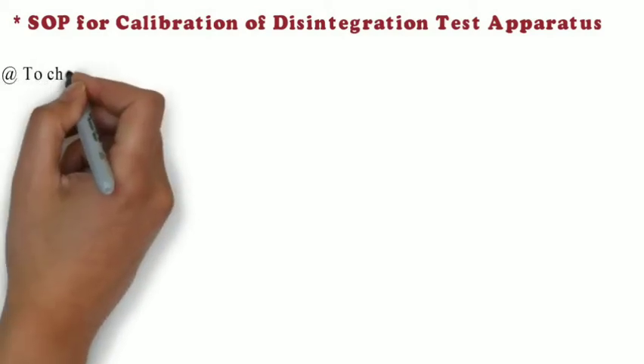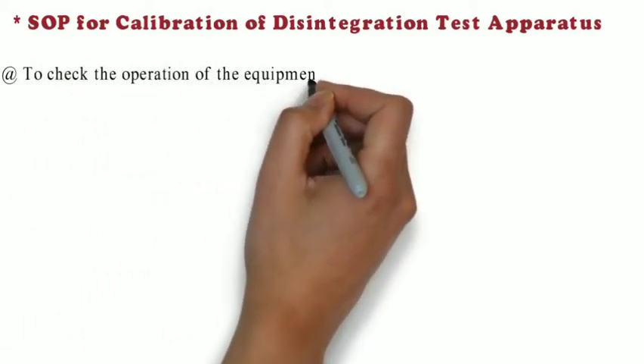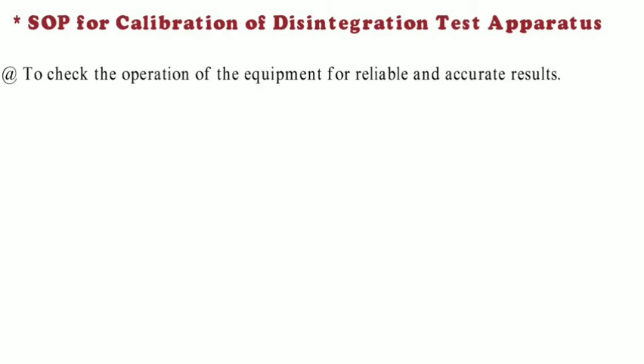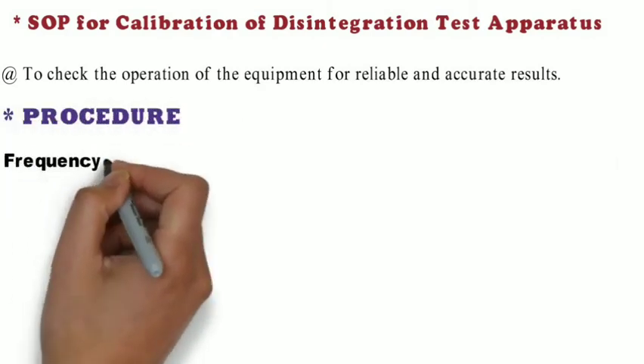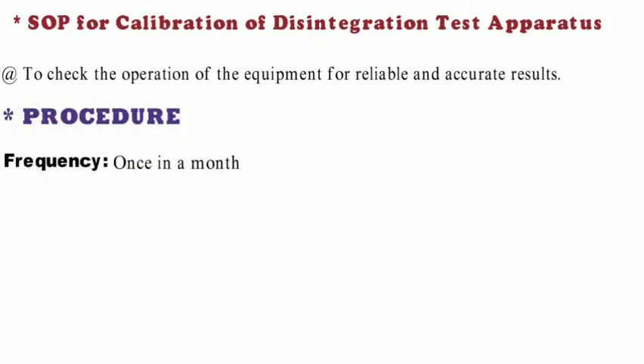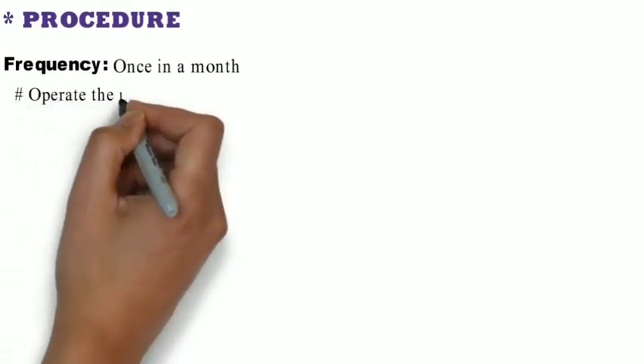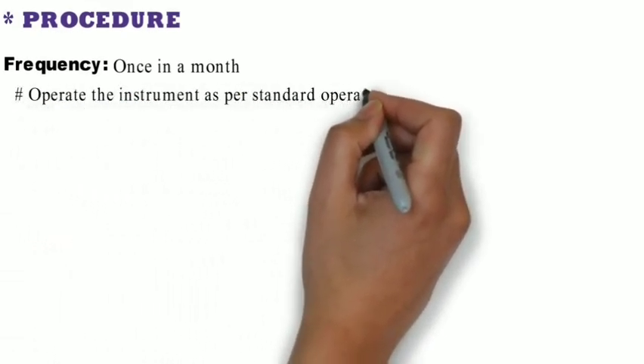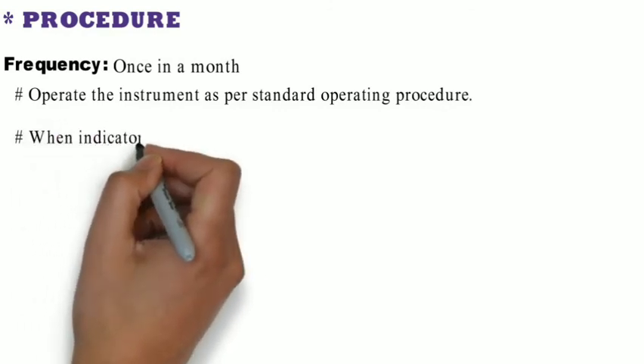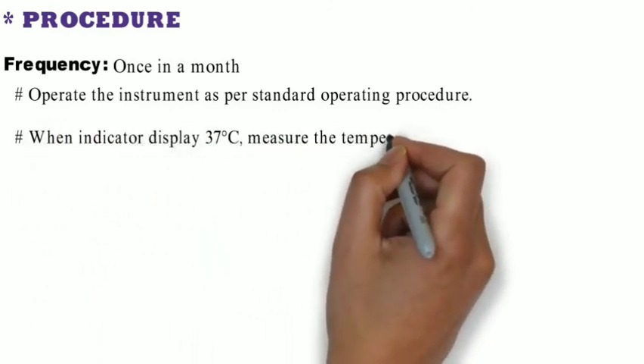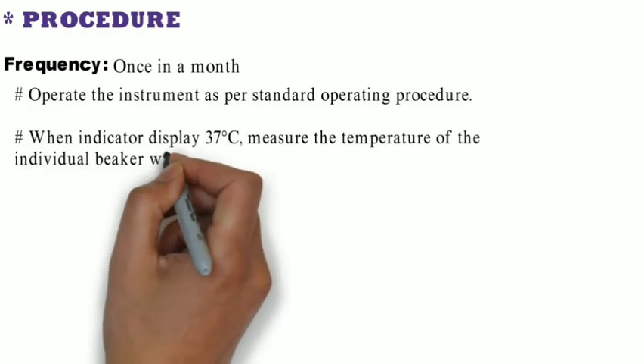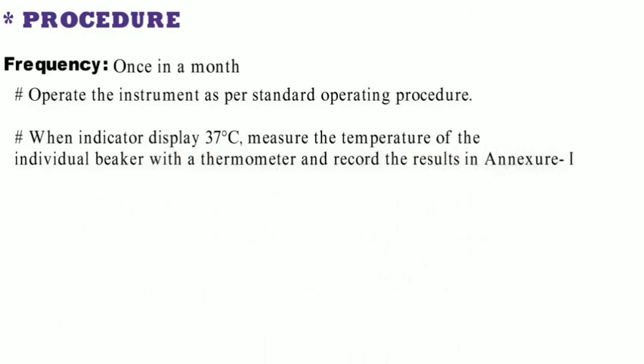This is the important portion of our lecture. The purpose is to check the operation of the equipment for reliable and accurate results. The frequency of the procedure is once a month. Operate the instrument as per SOP. When the indicator displays 37 degrees Celsius, measure the temperature of each individual beaker with a thermometer and record the results in annexure 1. As you know, there are 2 types of beakers, so we have to take the results individually.